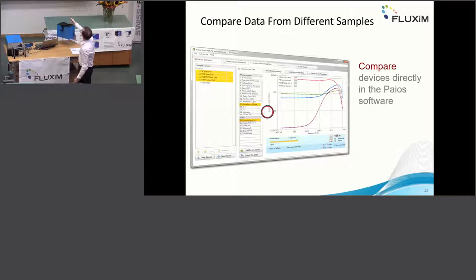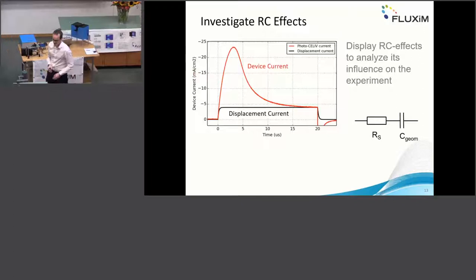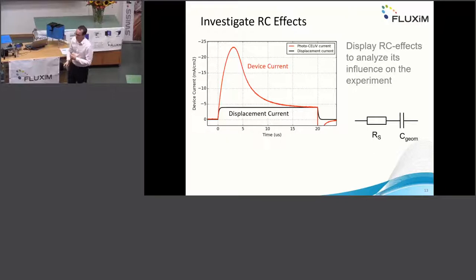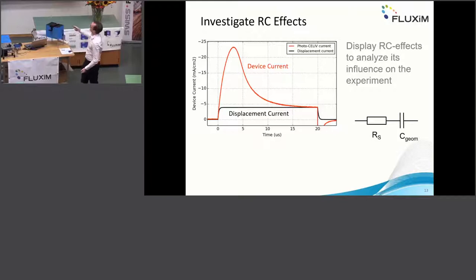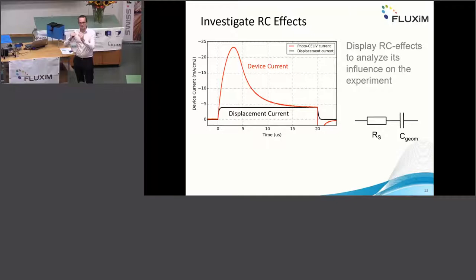We also have extra tools to help analyze measurement results. For example, you can show RC effects — you extract the series resistance R and the capacitance C, and then in a CELIV curve you can show the displacement current. The red curve here is the measurement and the black curve is the displacement current, so you can easily analyze what is displacement current and subtract it from the measured current.